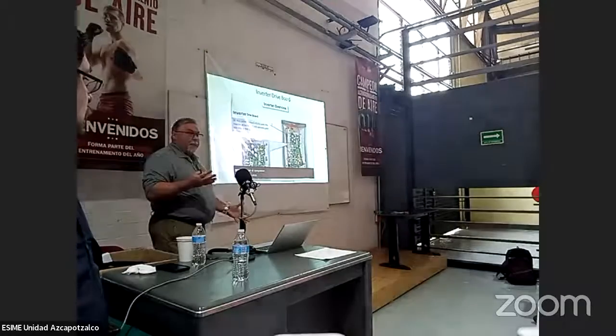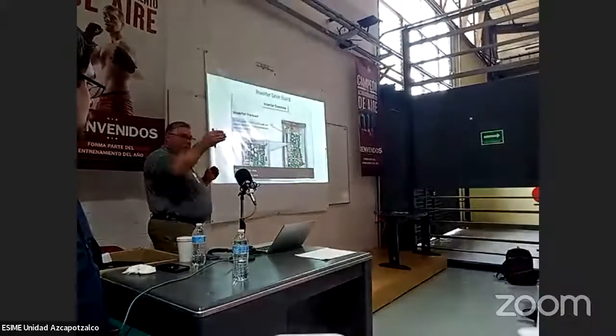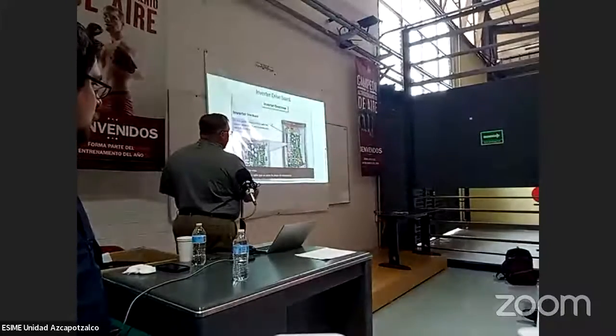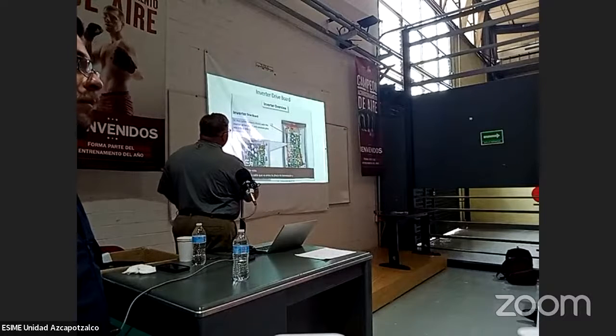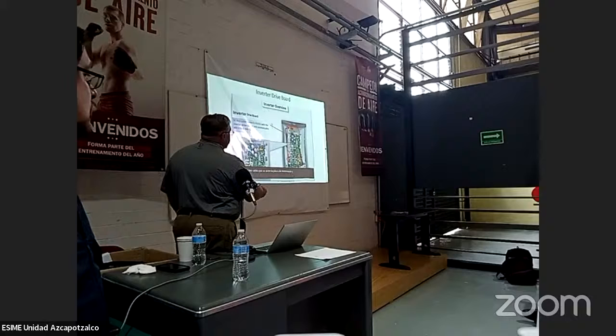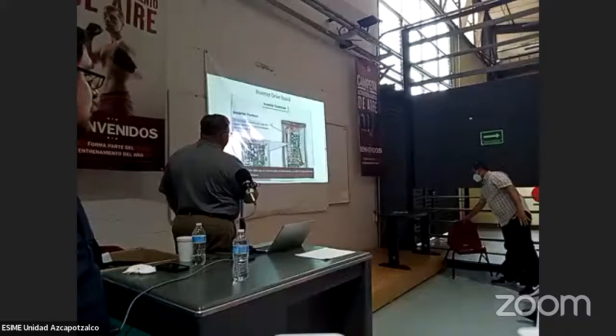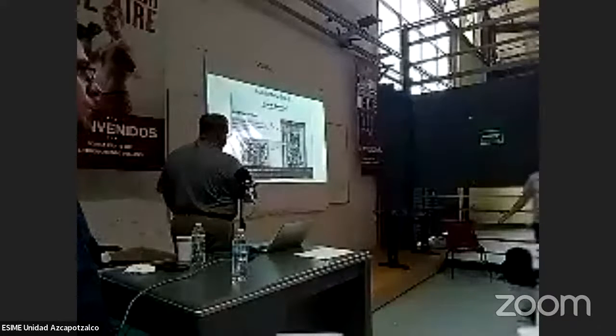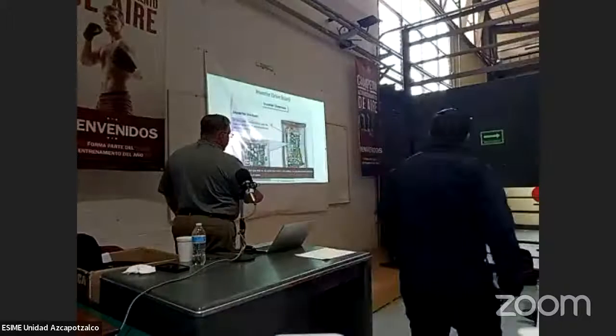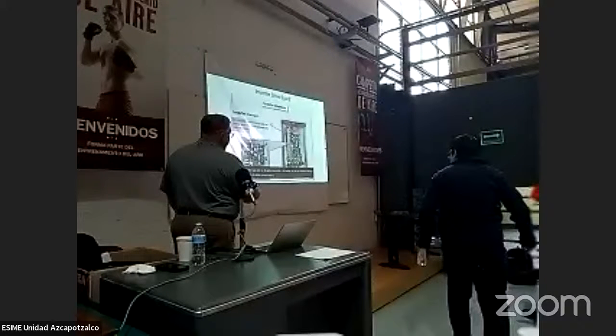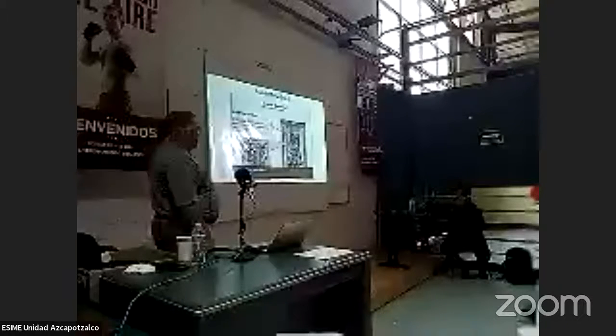Talk about that cable that goes between the drive board and the VSODU. This is that cable I'm talking about. So you can see the cable plugs in right here on the board. If you get a fault on that line, that cable most of the time is going to be the problem. Make sure it's plugging in properly, and make sure that it's connected properly. If not, then it's either going to be the drive board or the VSODU problem.